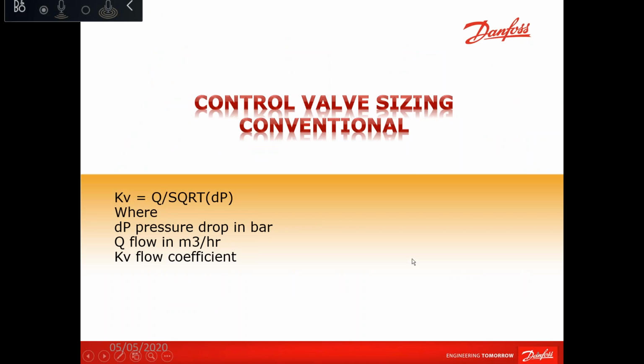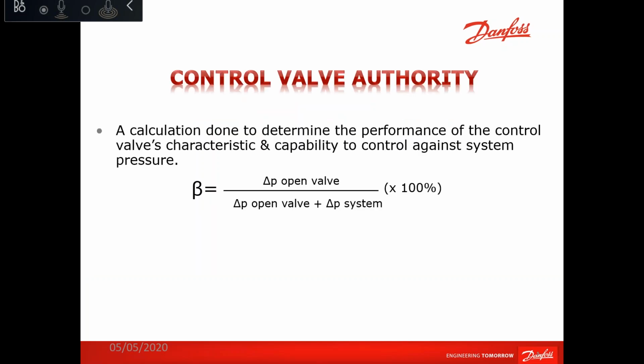So why is that happening? It's at the beginning, to start with, how we size the two-way valve. We take a normal sizing, the flow, which is equal to kV times the square root of delta P. Then what we need to know to select a two-way valve is the kV value, which is the flow coefficient, which is equal to flow divided by the square root of delta P, or pressure drop. So if we take an example, in order to achieve an authority of, in a two-way valve, the best authority we can have is 0.5 or 50%. We will explain why. So the authority is the capability of a control valve to maintain its characteristic, and it can be expressed by the formula delta P open valve divided by delta P open valve plus delta P system.